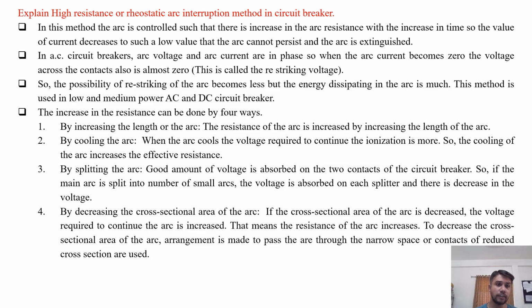To increase the value of the arc resistance, this can be done in four ways. One is by increasing the length of the arc. The resistance of the arc is increased by increasing its length because R is directly proportional to L. Now, by cooling the arc, the voltage required to continue the ionization is more, because as we cool it, we are processing deionization. So the arc may be quenched fast. The cooling of the arc increases the effective resistance.